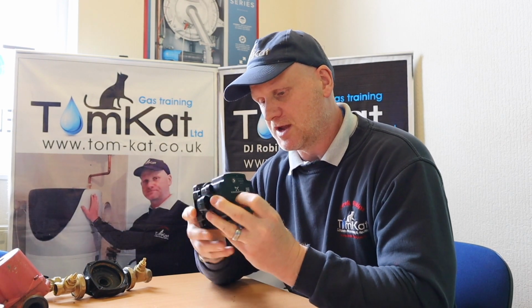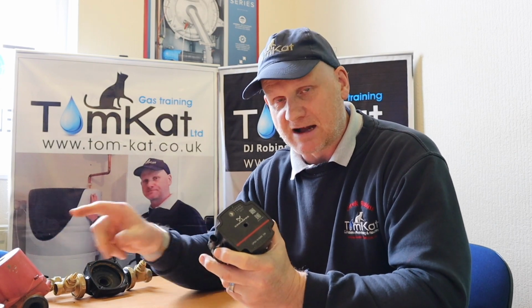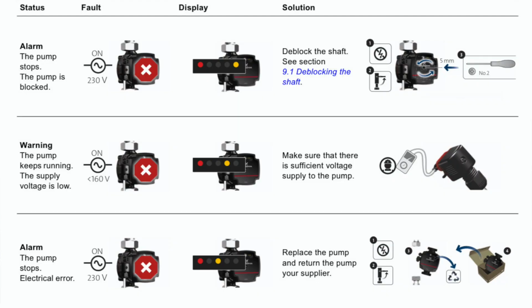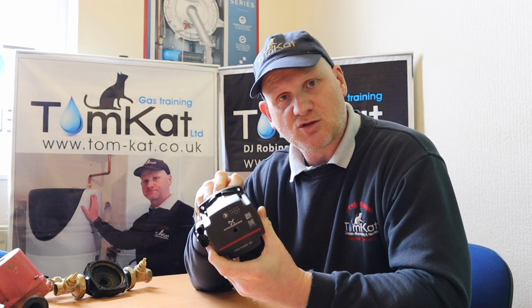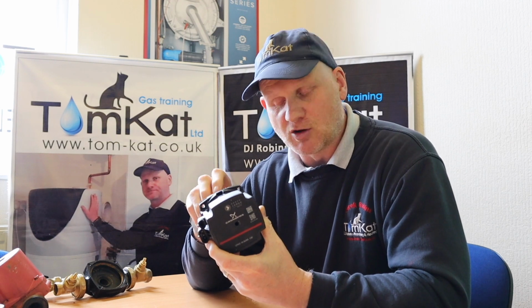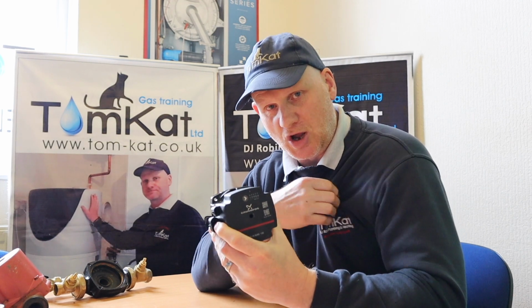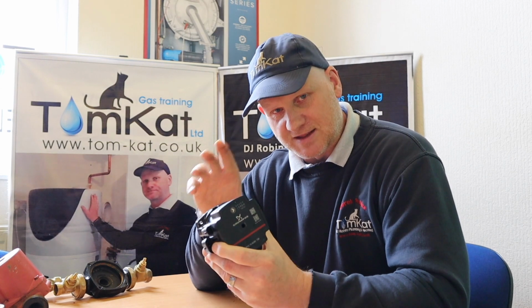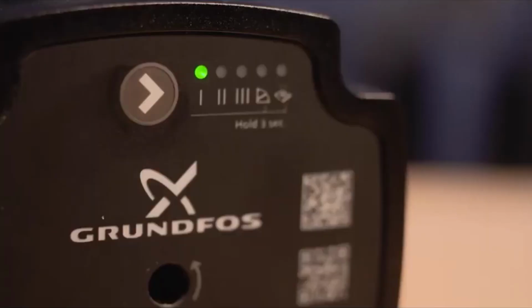Now what we've got to do is, if this seizes, this has a few fancy functions in it, better than that one. First of all is it has fault codes. What it also can do is it can try and free itself by turning itself backwards and forwards. So if you go to a boiler and you can hear it buzzing, then there's every chance it's trying to free itself. But it gives you some coloured lights on here which give you the different faults.